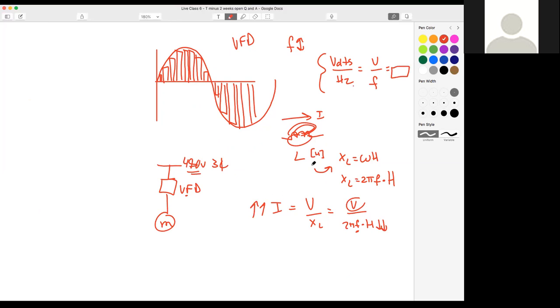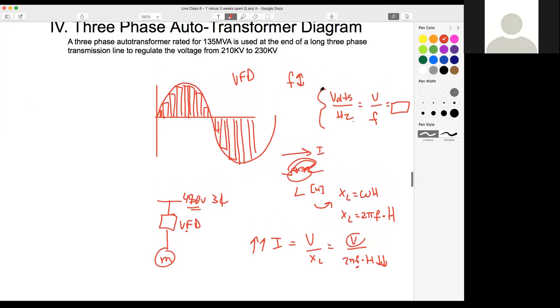So this relationship is really good to know. This is a fantastic qualitative question. You could see, okay, what happens if voltage is held constant, but the frequency is decreased without matching the voltage? Can the magnetic field grow beyond reason? Can it derate? That kind of thing. So that's a really good relationship to know.